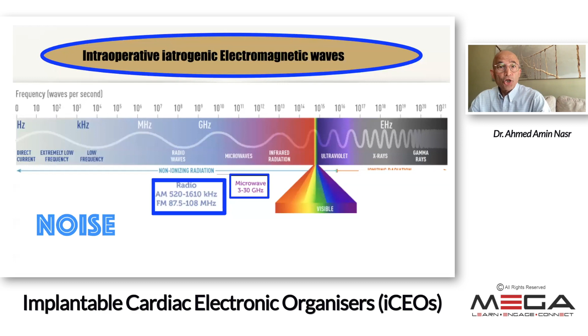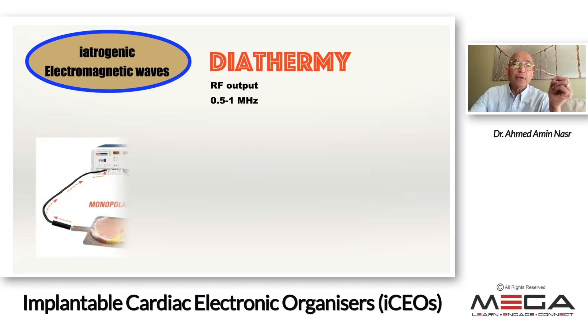Diathermy. In theater, we use radio frequency output of 0.5 to 1 megahertz in two forms, either bipolar form or monopolar form. The radio frequency electromagnetic waves pass through the tiny forceps of the monopolar, where it is very concentrated, making frequent vibrations of the ions of the tissues at 0.5 to 1 megahertz, making huge heat. And this heat is used for coagulation and cutting, hence this bloodless surgery.